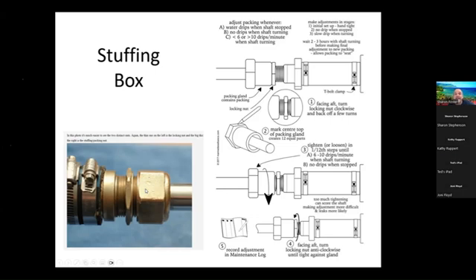Now, ideally, it says you want to adjust it to where with the shaft turning, 6 to 10 drips a minute. With the newer packing, I've seen it to where you can adjust it to where it's only 1 drip a minute. And I've actually seen it to where they don't have to drip as long as they're not getting hot. When I say hot, you should be able to put your hand on it and be able to keep your hand on it. It shouldn't burn you to the point where you have to pull away. As long as it's doing that, then you're fine. They don't have to constantly have water dripping out of them.